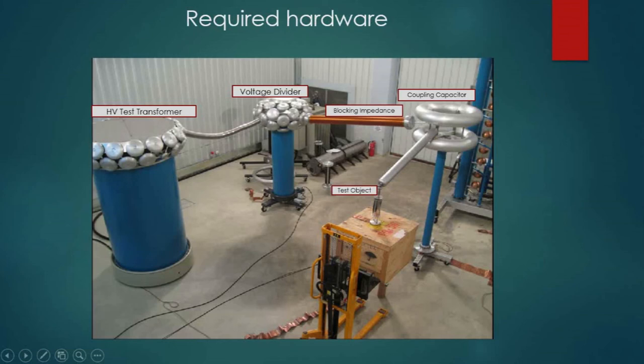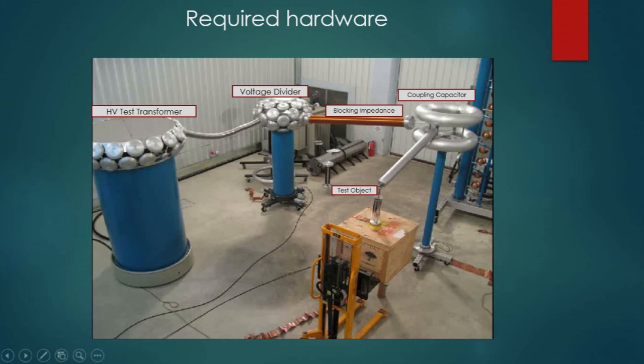For hardware requirements for offline PD measurements, the high voltage power supply is a high voltage test transformer. A voltage divider and blocking impedance are shown in orange, and the coupling capacitor is located nearby, connected to the test object. The exact configuration varies depending on the materials and the test object being measured, but this connection scheme represents the basic setup for offline PD measurements.